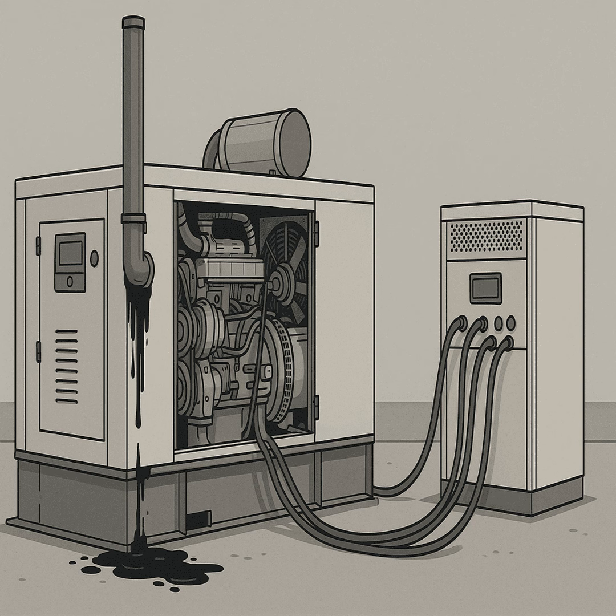Okay, so load banking, whether monthly or annually, depending on the tech, is key. How do facilities actually do this load banking? There are a few ways. Some larger facilities have permanent automatic load banks installed as part of their system. Others might have manual connection points for facility staff to use, or very commonly, portable load banks are used. Your generator service provider will bring a portable unit out during routine maintenance visits and perform the test then.